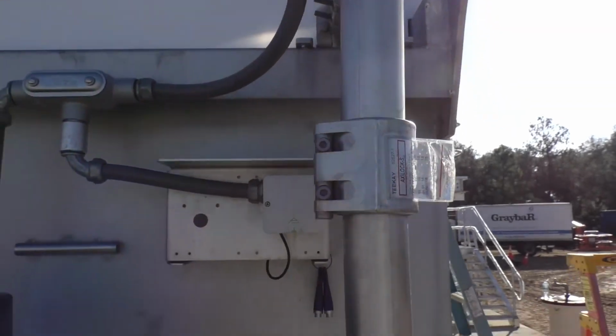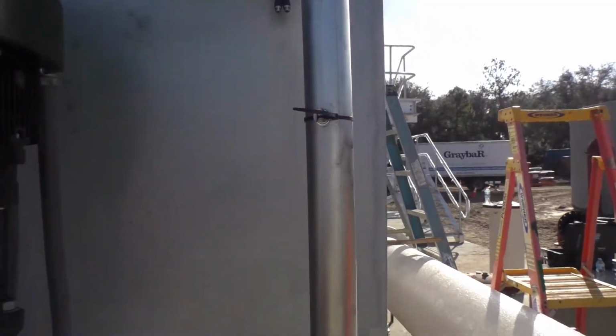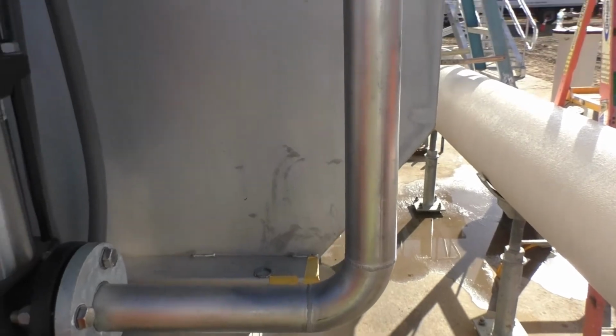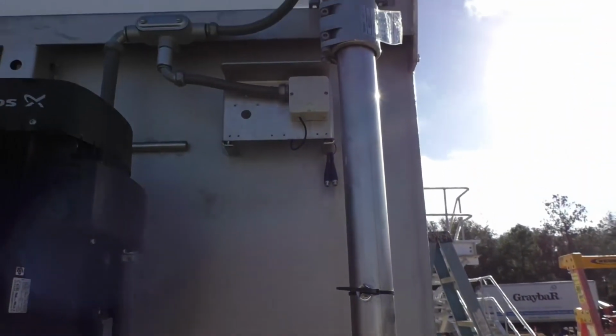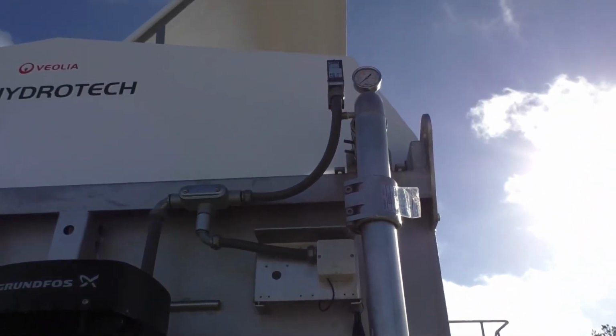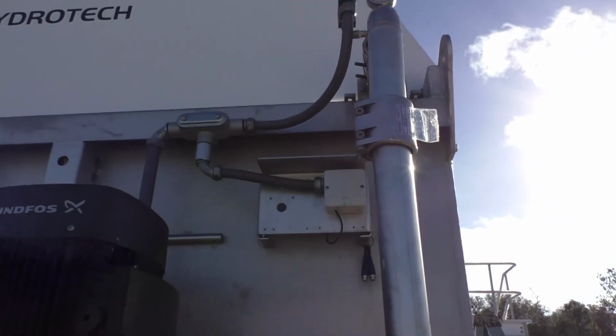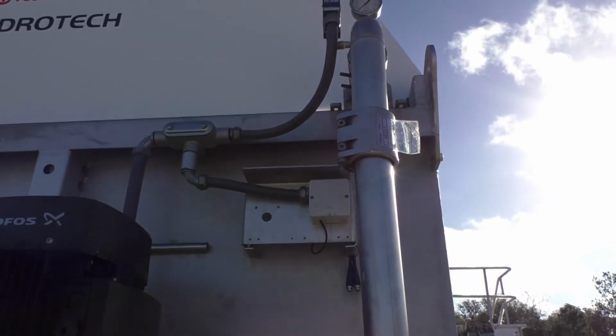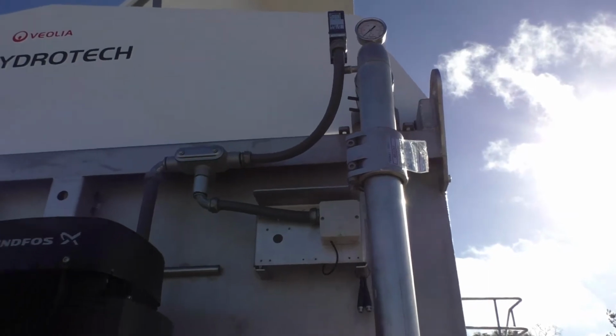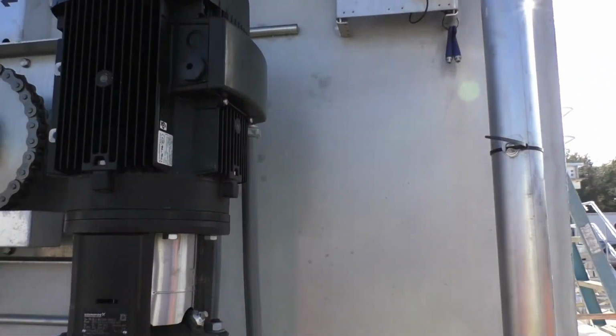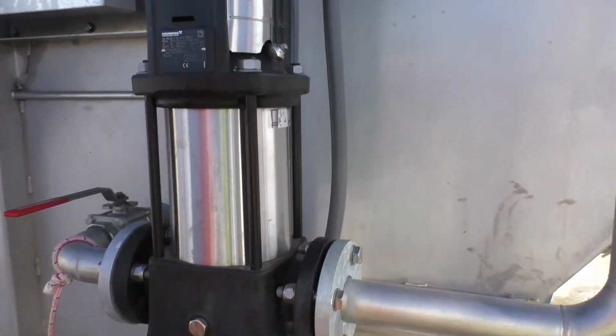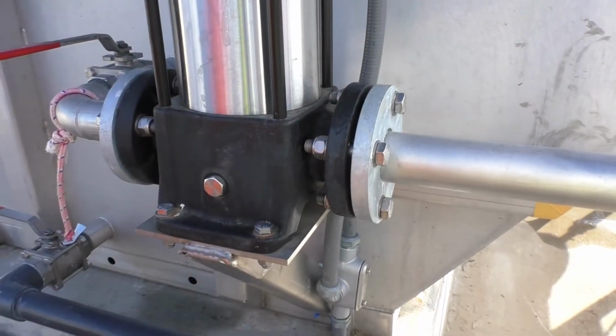Your backwash pipe, your gauge up there, the gauge up there to the top, you should be doing either 8 bars or 115 psi. The blue box is basically a low pressure switch. If it doesn't at least reach 50 psi in 5 seconds, it will shut down and you'll get a low level alarm. Basically just trying to keep from burning this pump up with no water.